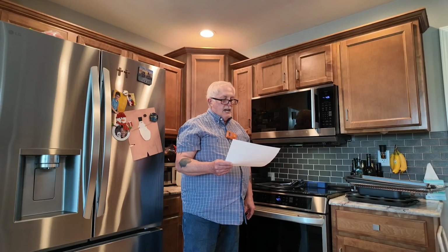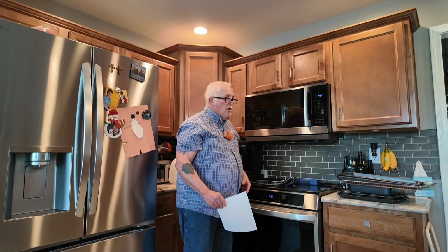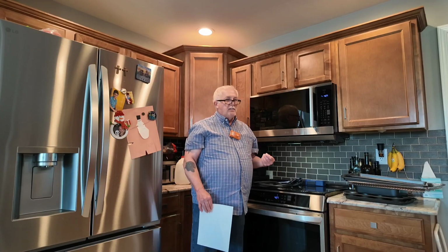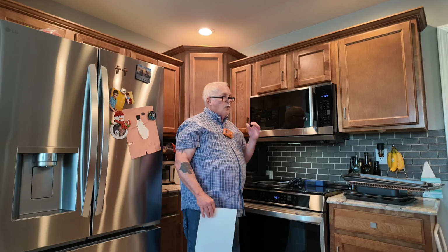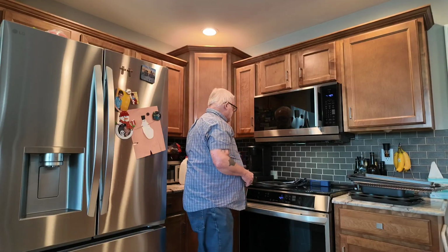Then it says candidate, turn the oven on. So we're going to turn the oven on. We would turn it on to 500 degrees. We would not turn it on self-cleaning. Just 500 degrees. And it says within 5 minutes or at the 5 minute or steady state point, we end up measuring for carbon monoxide.